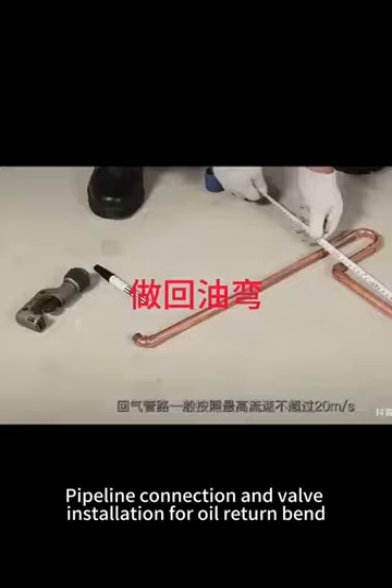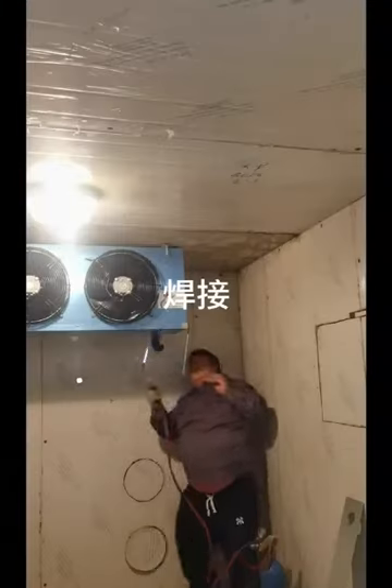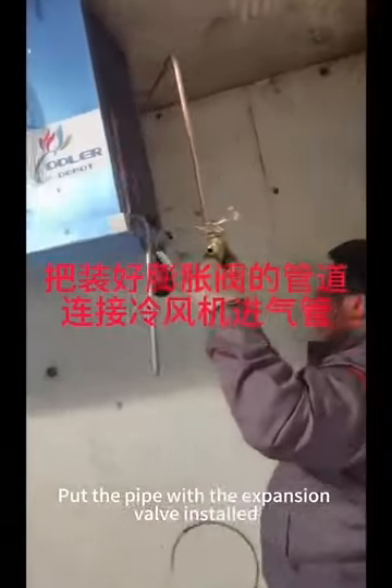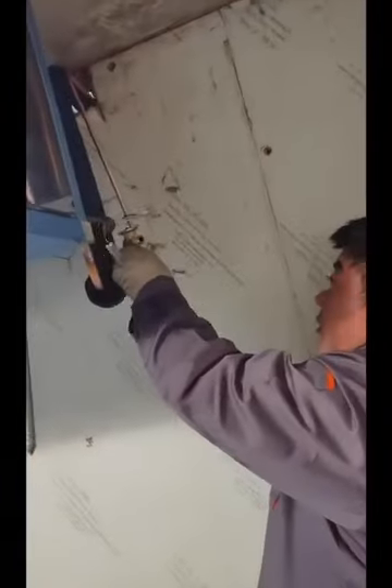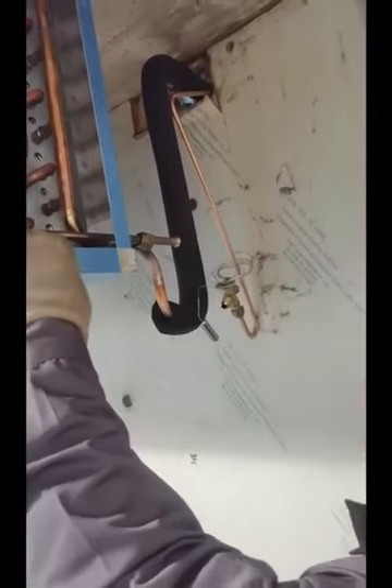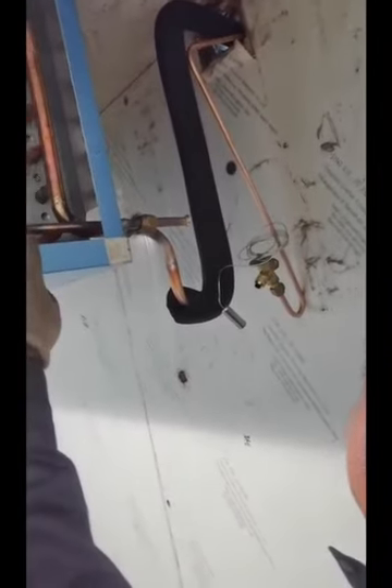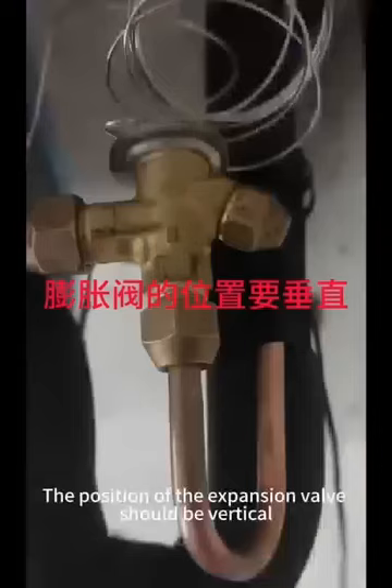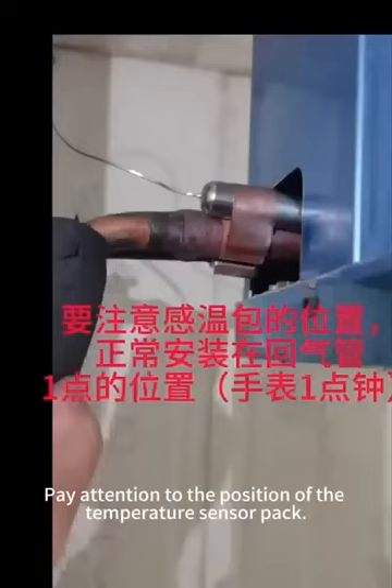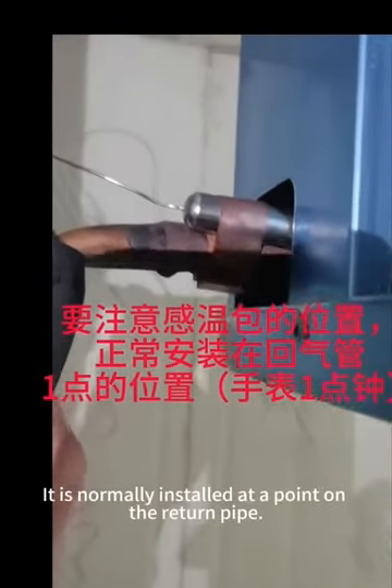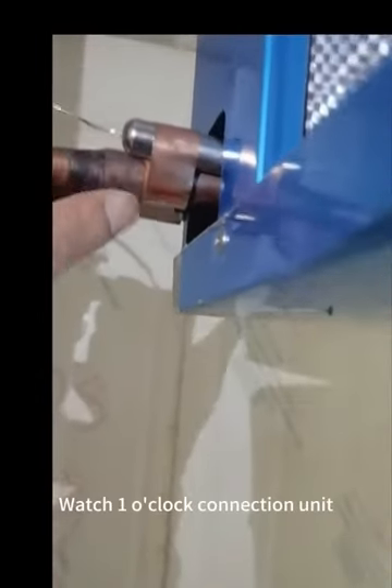Pipeline connection and valve installation for oil return bend. Good pipeline welding. Put the pipe with the expansion valve installed. Connect the air cooler intake pipe. The position of the expansion valve should be vertical. Pay attention to the position of the temperature sensor pack. It is normally installed at a point on the return pipe. Watch the connection unit.